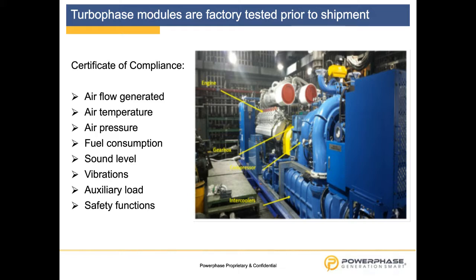Then we will monitor the fuel consumption to see the efficiency. We will have sound and vibration level acceptance. And we will of course have the auxiliary load and the safety functions, which are adapted to the site requirements. All of these tests will be witnessed by customer representatives, who go to the factory and see all the operations in the test stand. Once it is ready and factory acceptance certified, it will be dispatched to the site.